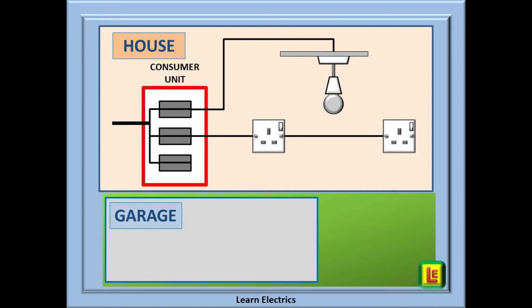The question now is: what types of circuits are these? Imagine electricity is travelling from the power station to the property. The lighting circuit from the consumer unit to the luminaires is the last or final leg of that journey. This makes the cables from the consumer unit to the light fittings a final circuit — this is where it ends. The same applies to the socket circuit, and the cooker and shower circuits. They are all the final part of the journey from the power station, with no more consumer units or fuses in the way.